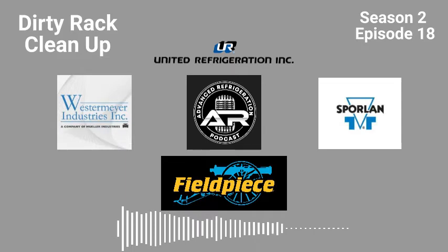Okay, so say you got a bunch of screens plugging up. We're not talking post-construction cleanup. We'll go over that separately. I'm talking like you have a rack, it's plugging screens, your suction temp's hot. Obviously a dirty rack is a problem. I mean, plugged filter dryers. This is the way I look at this.